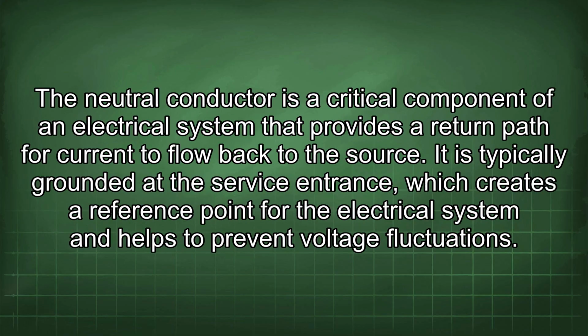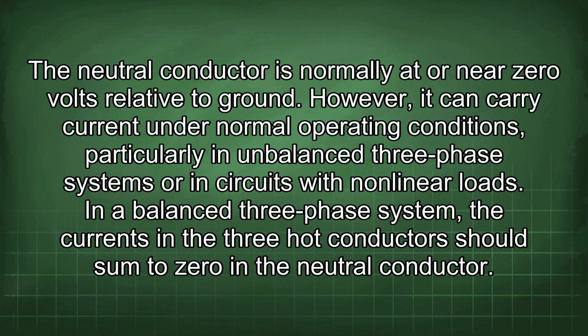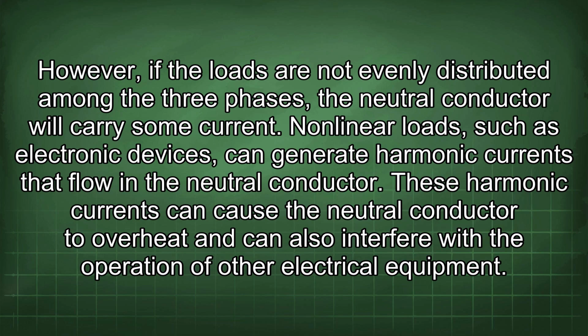The neutral conductor is a critical component of an electrical system that provides a return path for current to flow back to the source. It is typically grounded at the service entrance, which creates a reference point for the electrical system and helps to prevent voltage fluctuations. The neutral conductor is normally at or near 0 volts relative to ground. However, it can carry current under normal operating conditions, particularly in unbalanced three-phase systems or in circuits with nonlinear loads. In a balanced three-phase system, the currents in the three hot conductors should sum to 0 in the neutral conductor. However, if the loads are not evenly distributed among the three phases, the neutral conductor will carry some current. Nonlinear loads, such as electronic devices, can generate harmonic currents that flow in the neutral conductor. These harmonic currents can cause the neutral conductor to overheat and can also interfere with the operation of other electrical equipment.